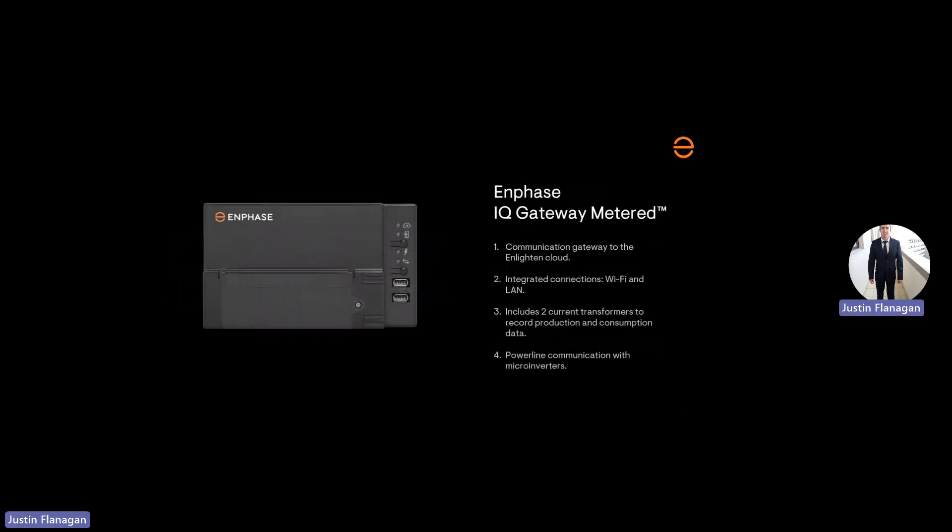The next device is the Gateway, previously known as the Envoy. The Gateway collects all the data from the microinverters through power line communication, known as PLC, and sends the information to the Enlighten platform for the end user. The same Gateway can be used for single or three phase connections. Connection types to connect to the Internet are Wi-Fi, Ethernet, or cellular. Also, with the Gateway, we are able to connect CTs directly onto it so we have accurate readings of our consumption, either import or export back to the grid, and our production values from the PV array.